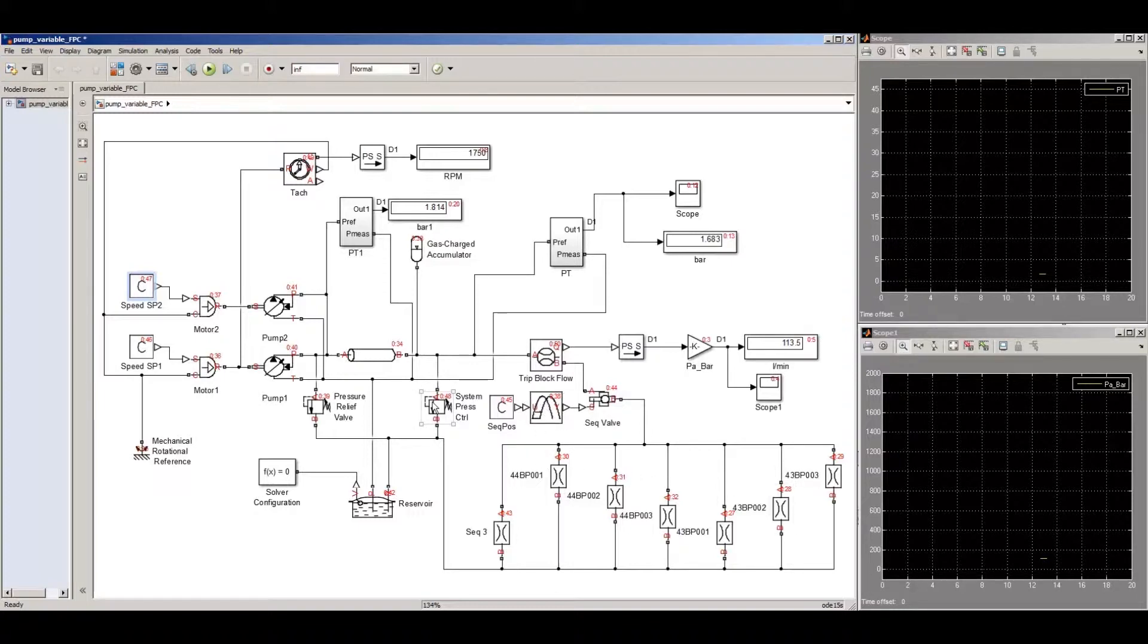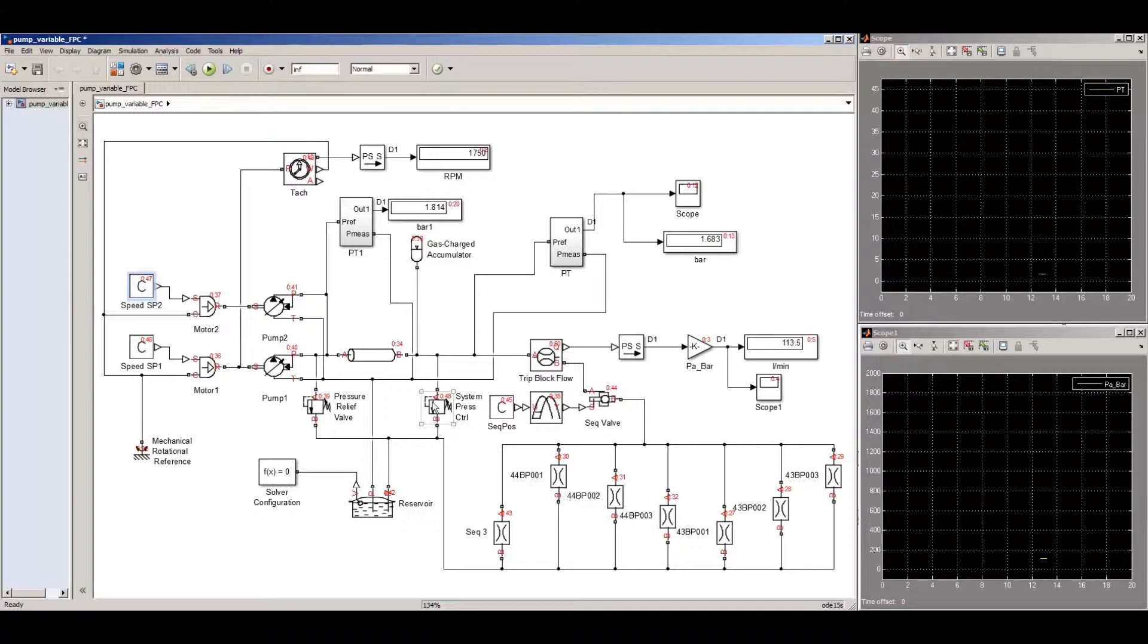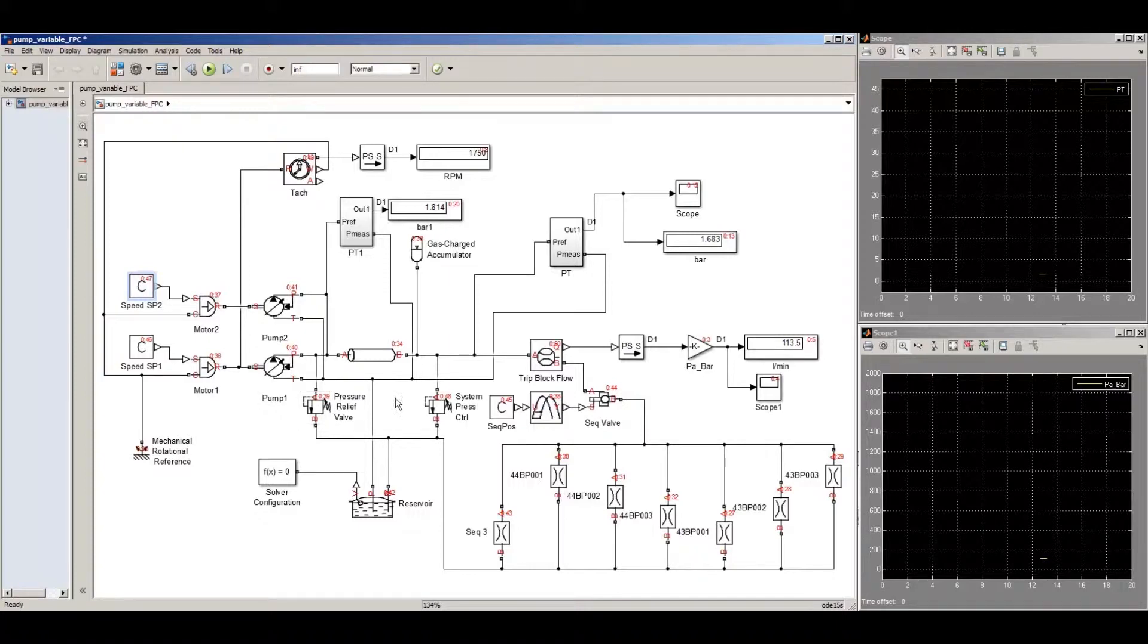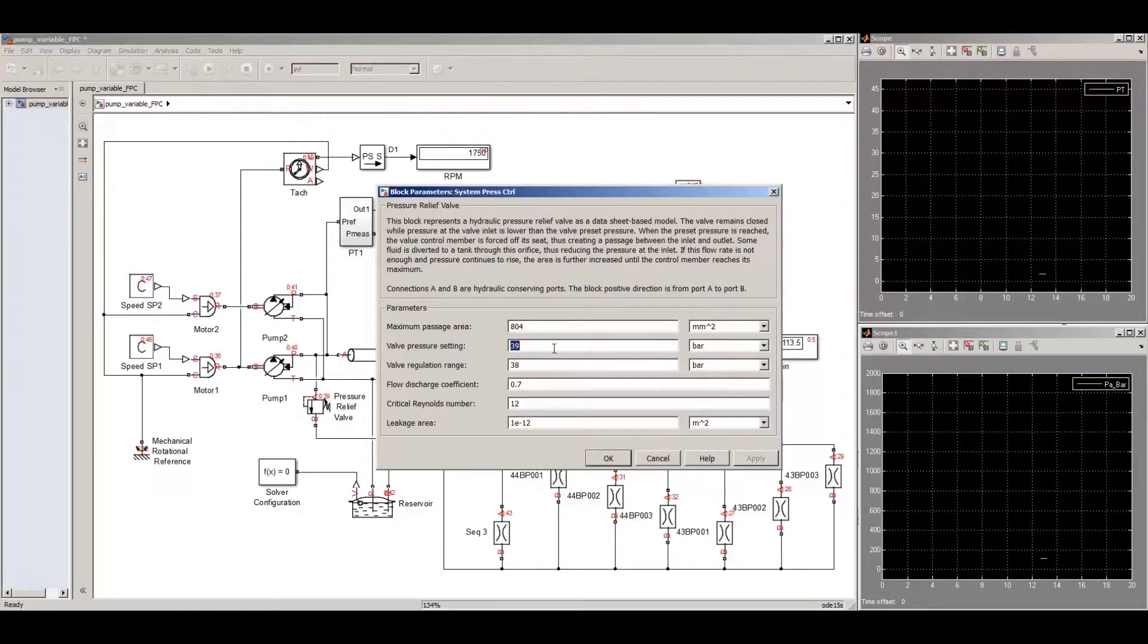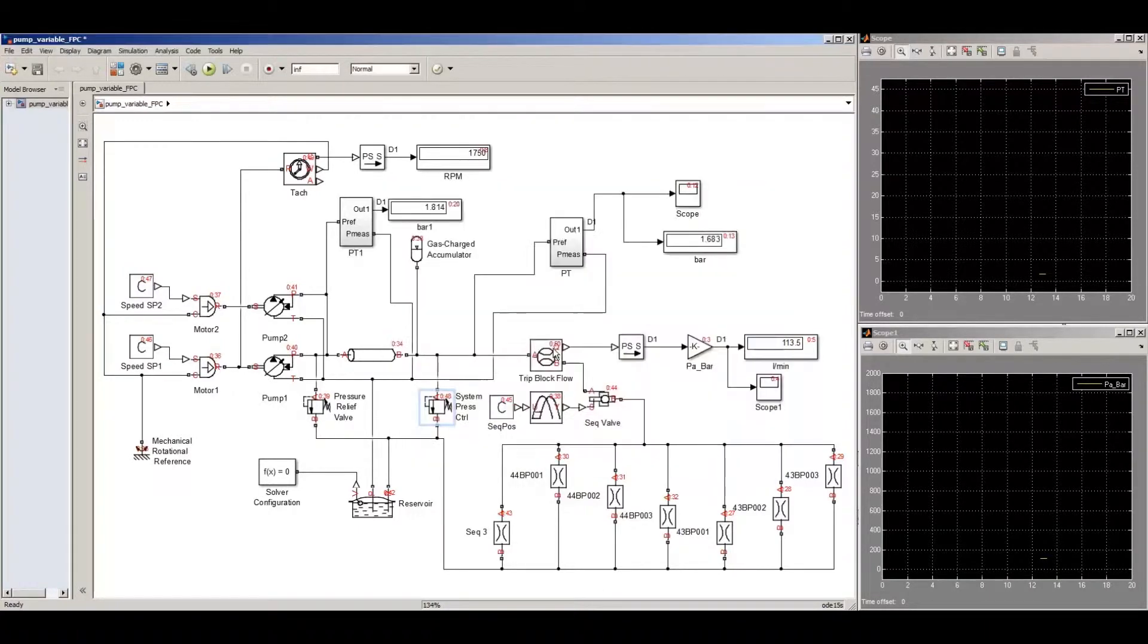The relief valve, actually called the system pressure control valve at the end of the system, is set up with a set point of around 40 bar. We'll open that one up and see what it looks like. It shows to be 39 right now, so we can set that at 40.